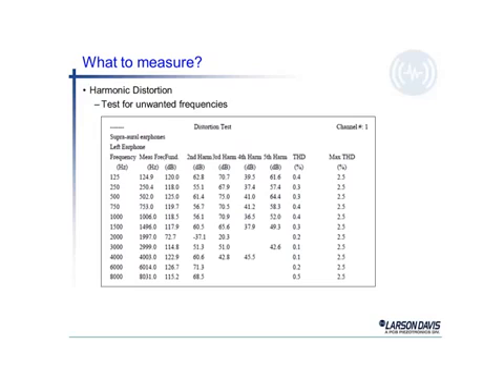Harmonic distortion is sometimes referred to as total harmonic distortion, or THD. The maximum THD allowed for different frequencies by the standard is 2.5%. Most electronics today can easily accomplish that. And so again, using our example near 1000, we see the level, we see harmonics, and all of those totaled up, giving us a total harmonic distortion of only 0.4%, well within the 2.5% that's allowed.